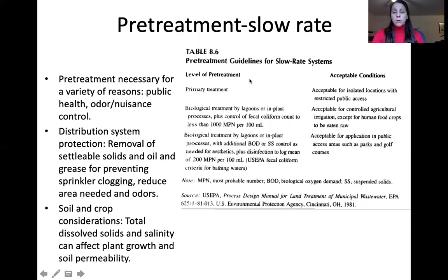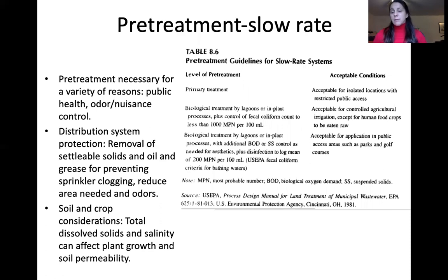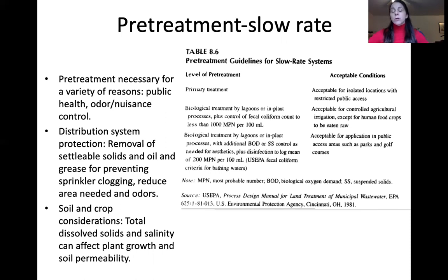For pre-treatment levels: primary treatment alone is only acceptable at isolated, restricted-access locations such as spraying in woods. Biological treatment by lagoon or in-plant process with a fecal count under 1,000 MPN per 100 mL is acceptable for agricultural irrigation, except for human food crops eaten raw. With additional controls plus disinfection to under 200 MPN per 100 mL — the fecal coliform limit for bathing waters — application in parks and golf courses is permitted.